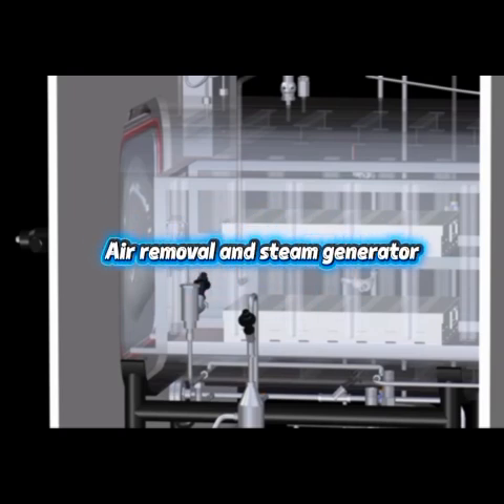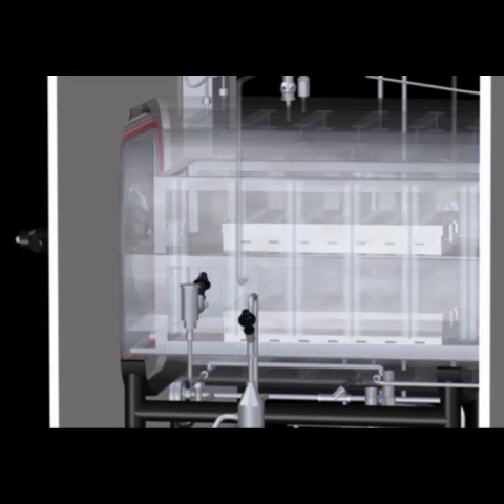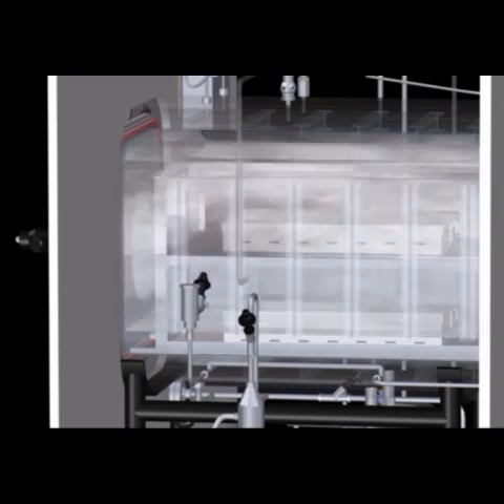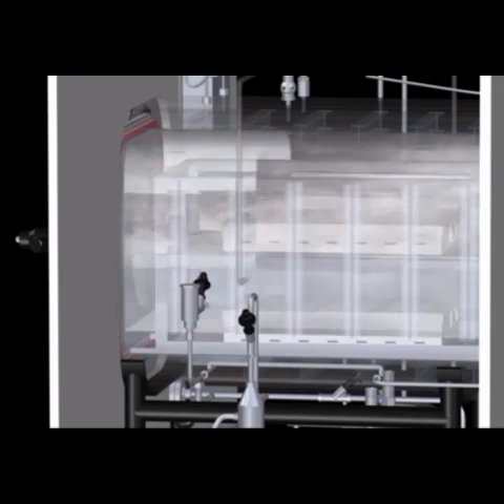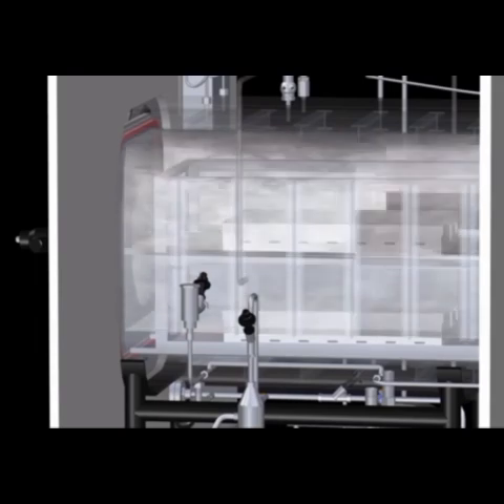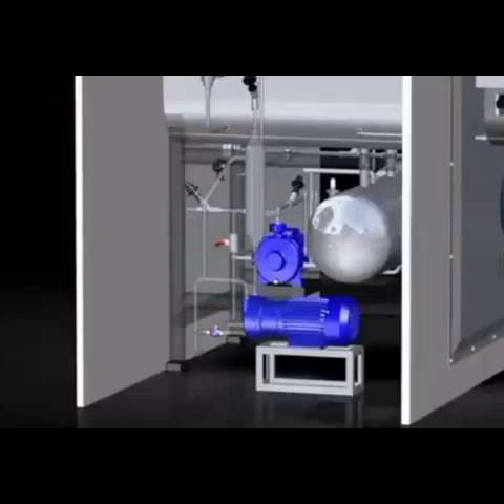The third step is called air removal and steam generation. The autoclave generates high pressure saturated steam. Air inside the chamber is removed, allowing steam to penetrate all surfaces of the instrument evenly.